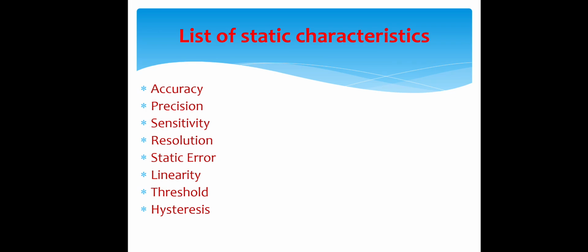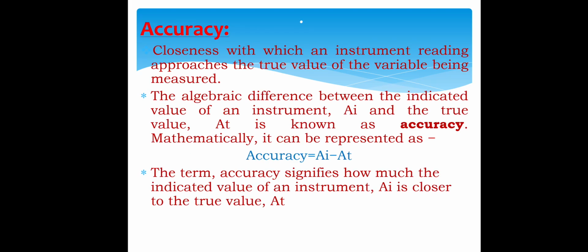Those static characteristics are accuracy, precision, sensitivity, resolution, static error, linearity, threshold, hysteresis. These are the items in static characteristics. Accuracy is the closeness with which an instrument reading approaches the true value of the variable being measured. The algebraic difference between the indicated value of an instrument and the true value is known as accuracy. So, the difference between the indicated value of the instrument and the true value.